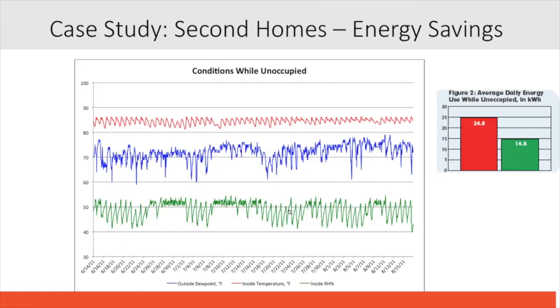This was a second home energy savings study we did down in Ocala in the Villages, and they set their thermostat at 85 degrees. We had the RH set at, I think it was 50 or 55, for the summer while they were back in the Northeast, because all we cared about was controlling the relative humidity while they were gone. And there was a 40% energy savings from the year before, where they tried to use a humidistat to control the AC to run, versus a dehumidifier, because again, we just want to prevent any microbial growth typically when we have unoccupied homes.